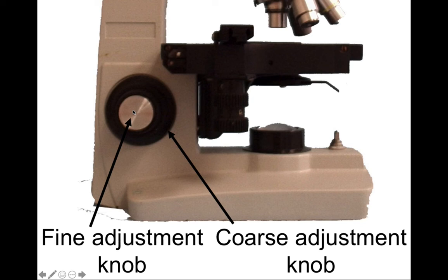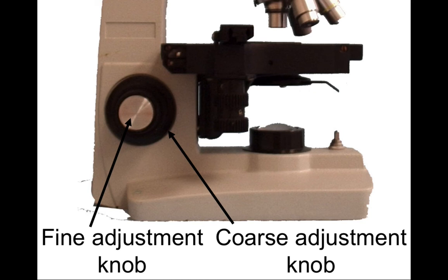The fine adjustment knob sticks out a little bit, and you'll be able to use them separately. The coarse adjustment knob produces a noticeable visual change in the distance of the stage from the objective lens, while the fine adjustment knob will not produce a visible difference in that distance. The coarse adjustment knob is typically what you'll use when readjusting microscope slides. You always want to make sure the stage is as far away as possible from the objective lenses so as not to damage or scratch them — this gives you more working space.